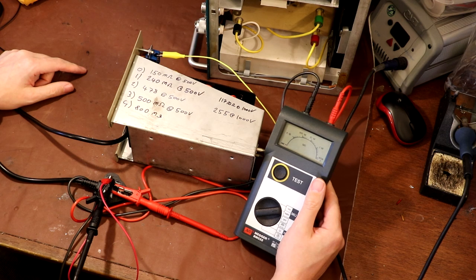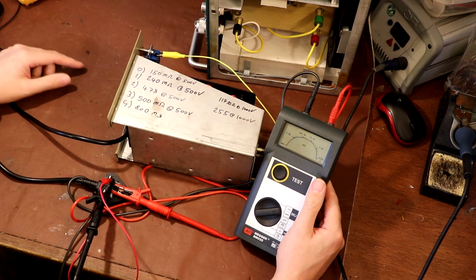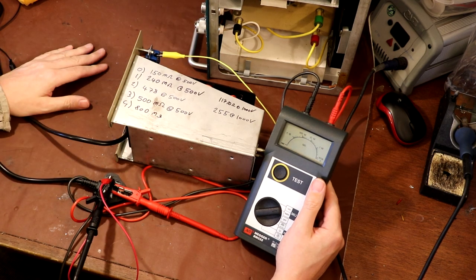Now it would actually be slightly higher than that because I probably should have used the peak of the mains waveform rather than the RMS value, but still it wouldn't have been double. It maybe would have been 7 or 8 microamps, but it certainly wouldn't have been the 30 milliamps that it actually took to trip out my earth leakage circuit breaker in my consumer unit in my main supply. However, I've spent quite a lot of time looking at this and I really couldn't find a problem with it.